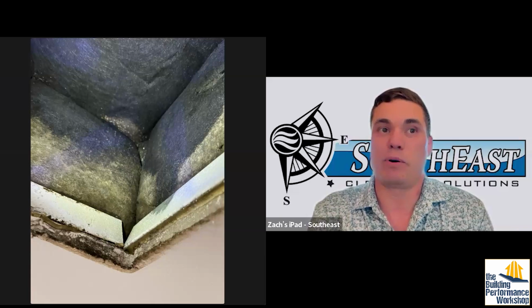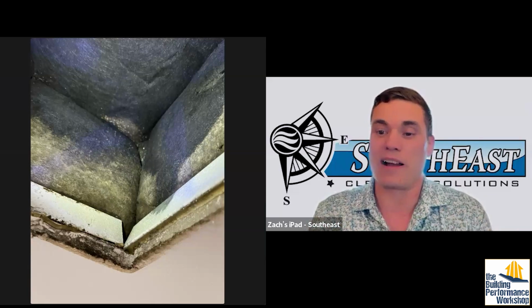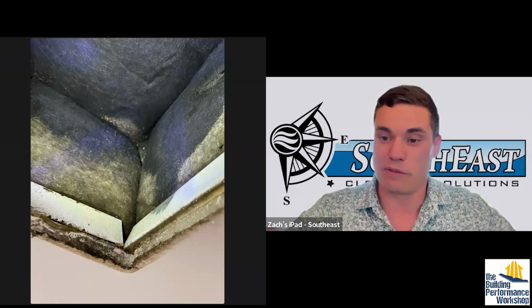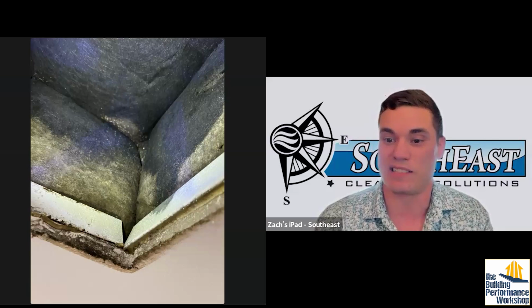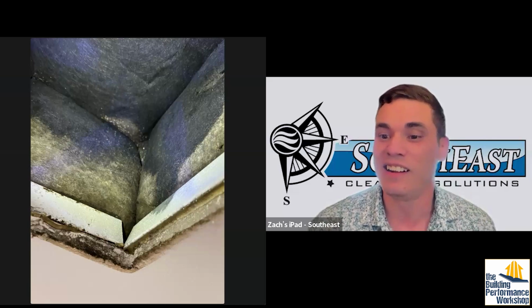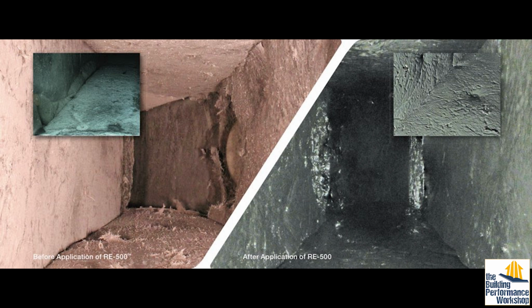And you'll see this when you pull the fiberglass around a vent boot. When you start to remove it and pull it away, you'll see that it's kind of black and brown because it's been acting as the filter of the attic air coming into the airstream. And a product that's trying to prevent condensation is also providing a medium. I've got a little pocket microscope that I use. When you look at it very closely, it looks like a filter. The texture of it is very rough and it's very much like a filter. So what happens is it latches on to the dust that collects in that airstream at that friction point.